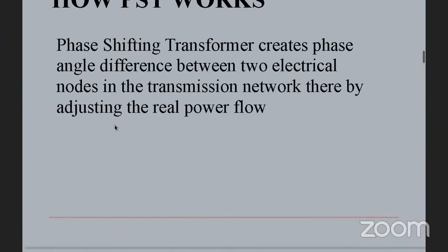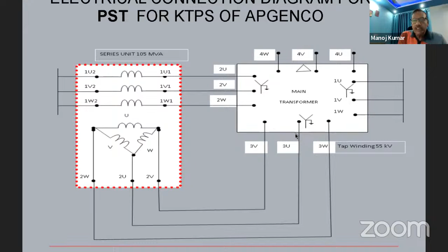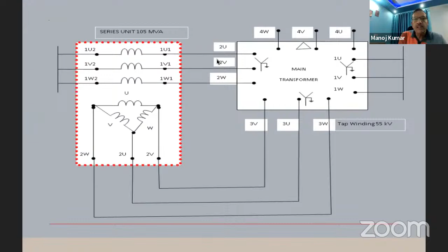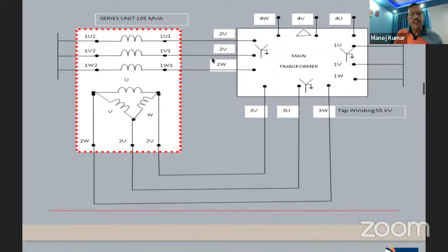Here you can see that for Kothagudam we have put two transformer units. One is a 105 MVA series transformer, and one is a 400 kV ICT. In the ICT, one more additional control winding has been provided. This gives a voltage which is injected into the series transformer winding. This controls the phase angle between the two ends of the transformer, which is the ICT.